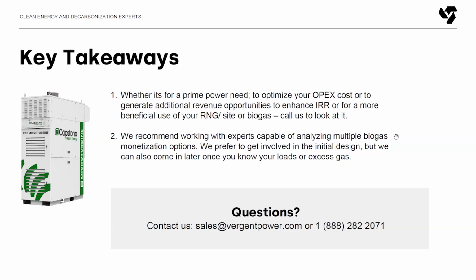Yeah, all those technologies have their positives and negatives. Certainly if you're operating a significant part of the year, call it 6,000 hours or more, you'll find the microturbine an extremely good option, just for the fact that the low maintenance interval means you're never going to get caught into the high OpEx costs you'll get with some of those other technologies. Also the reliability aspect - our sites operate 99.5% uptime per turbine, so the whole site is typically around 100%. You might have a shutdown here and there per turbine, but that's much higher uptime than a lot of those other technologies.